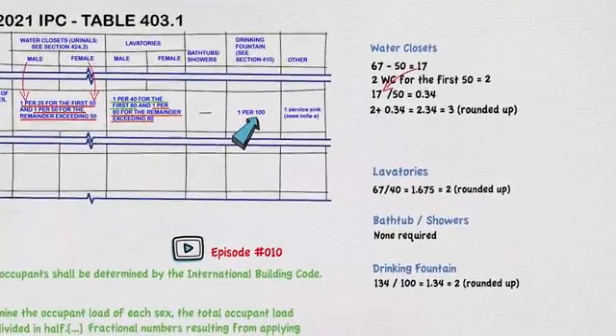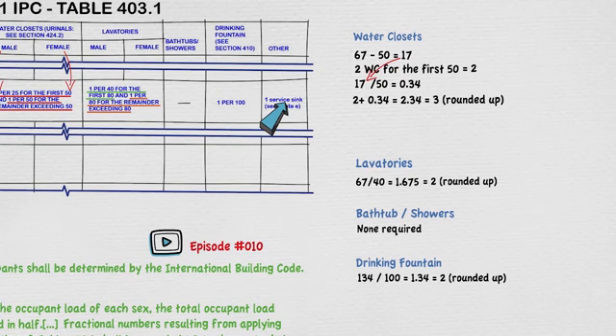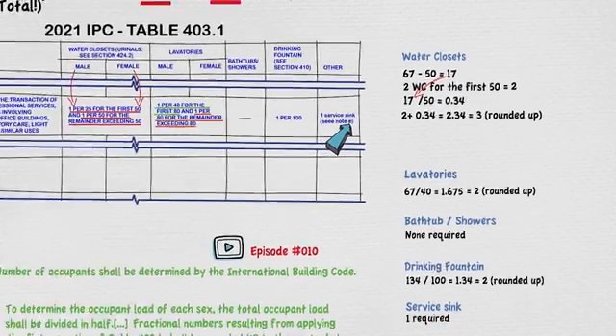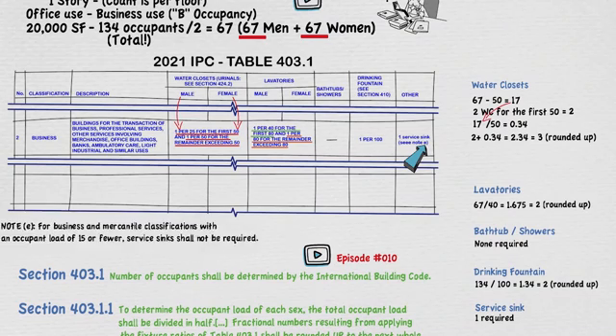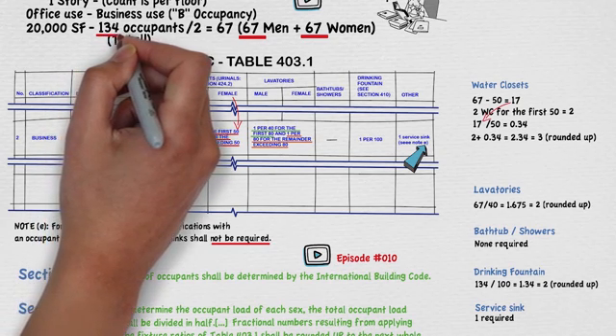Last but not least in the table is the 'other' column. Looking at the requirements, we see the service sink — often called a janitor sink or mop sink. This simply states one service sink regardless of the occupancy count or size of the floor. There is a note stating that for business and mercantile classifications with occupant loads of 15 or fewer, service sinks shall not be required. But our project has way more than 15 occupants.